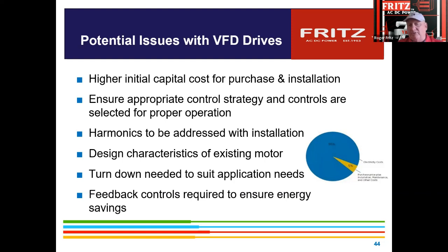The ensuring the proper control strategy, so that they get installed, they get properly controlled to a sensor and/or BMS system. We work hand in hand both with the building management systems and with the controls. And at the end of the day, they can operate on their own. You've got a pump running a pressure regulation. It can all sit there and operate without even having to be tied to a BMS system and still save the same amount of money.